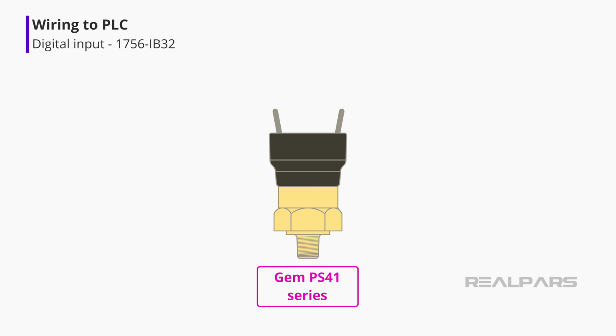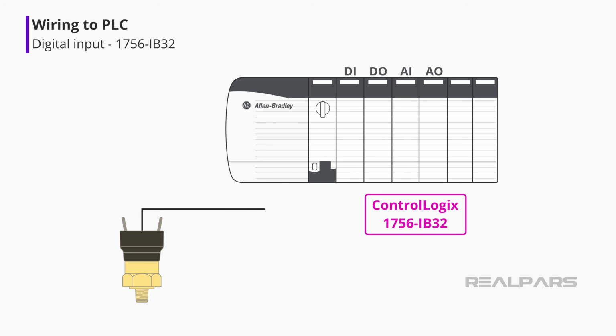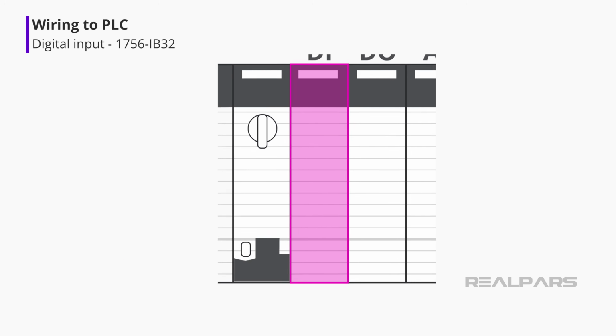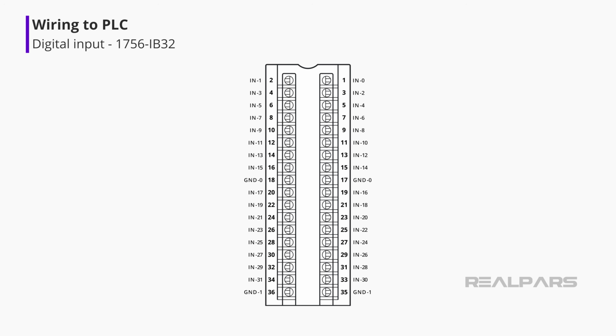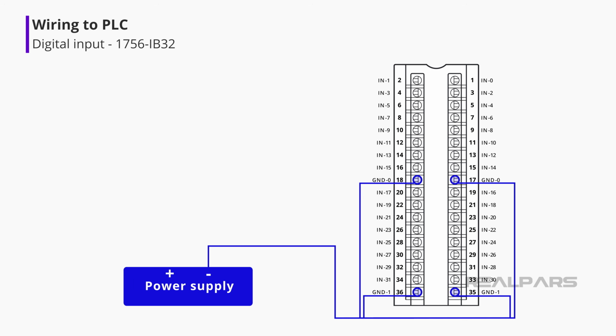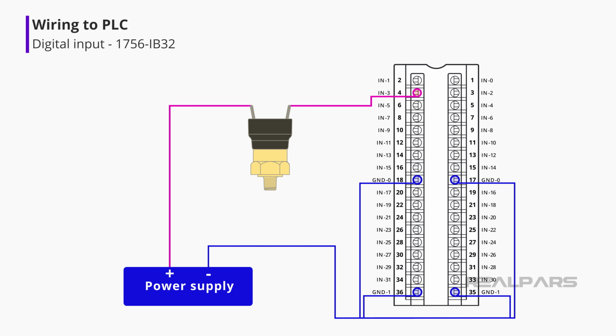Alright, let's wire a GEMS PS41 series pressure switch to input 3 of a ControlLogix 1756-IB32 digital input module. All of the ground terminals on the 1756-IB32 module must be wired together and connected to the negative DC terminal of the 24-volt DC power supply. So, we need to connect terminals 17, 18, 35, and 36 and wire them to the negative DC terminal of the power supply. Because the pressure switch is not voltage dependent, it doesn't matter which wire goes to the positive DC terminal of the power supply and which wire goes to terminal 4 of the input module. So, take your pick and connect the two wires.